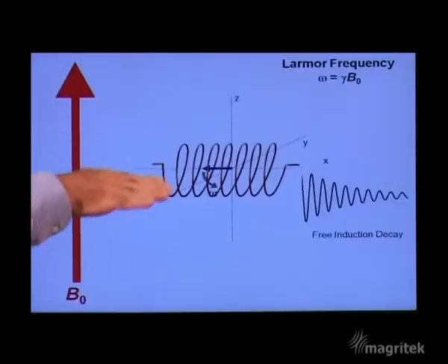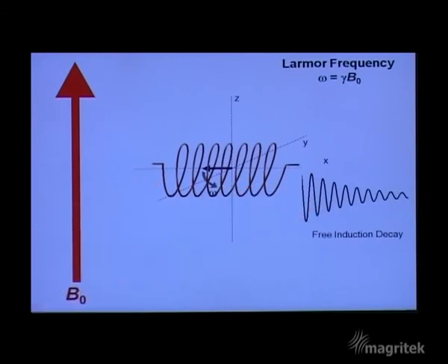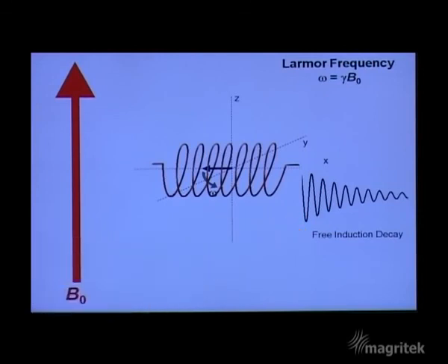And that same coil is used not only to transmit to the nuclei but also to receive the signal, to pick up that electromotive force, that oscillating voltage, as the nuclear magnetisation precesses around in the coil, with the signal gradually decaying away with time as the spins come back to thermal equilibrium, and we call that signal which decays with time the free induction decay.